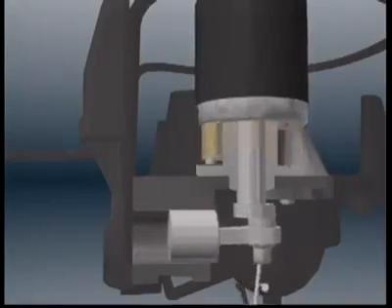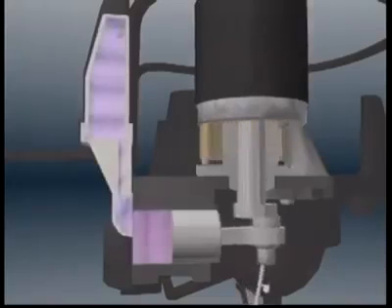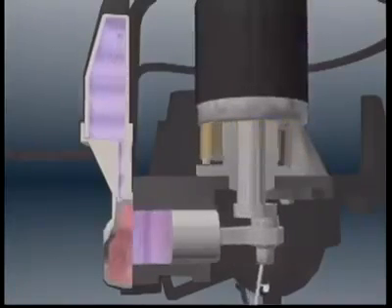As the piston strokes back, the pull that it creates draws refrigerant in from the evaporator through the suction muffler. The suction muffler reduces the noise refrigerant makes flowing into the compressor. As the piston pushes forward, the exhaust valve opens and refrigerant heads out toward the condenser.